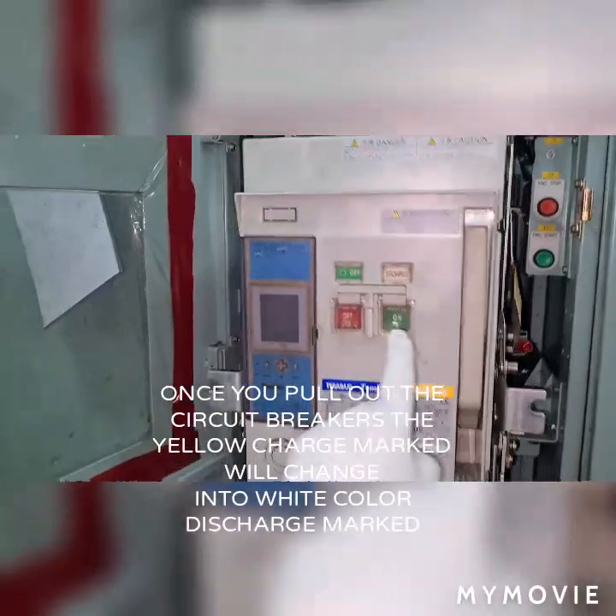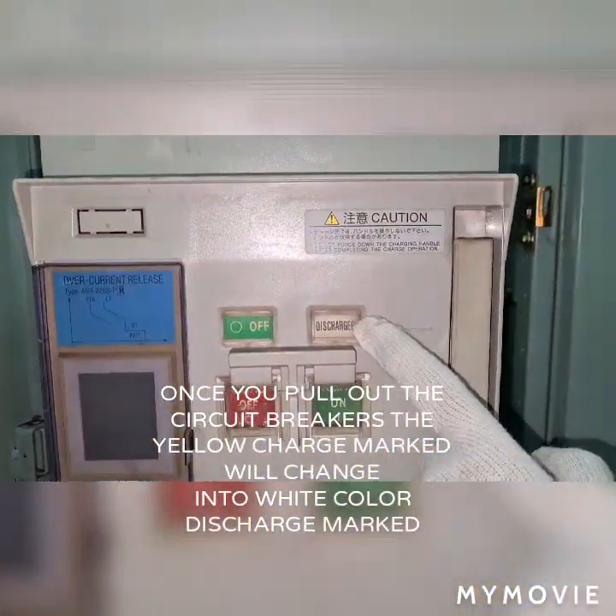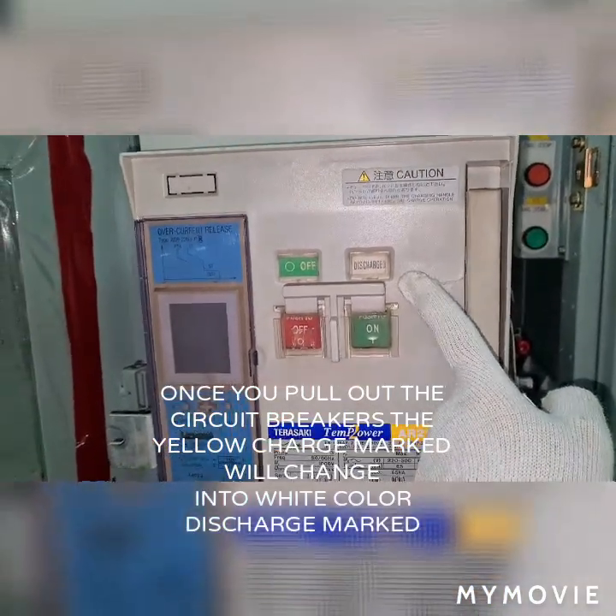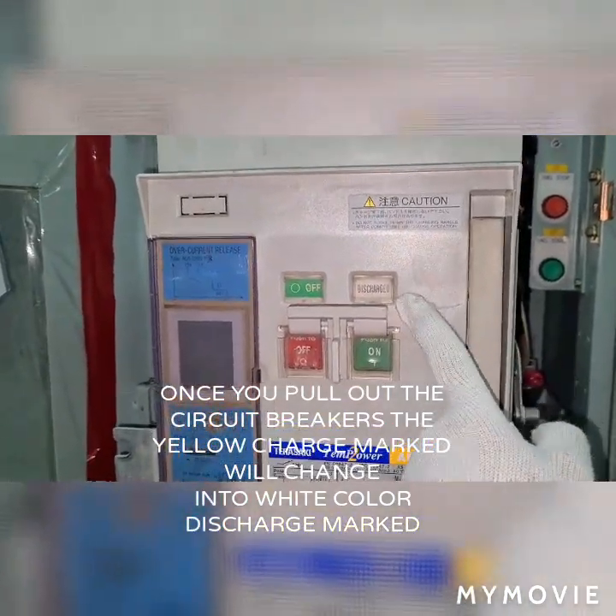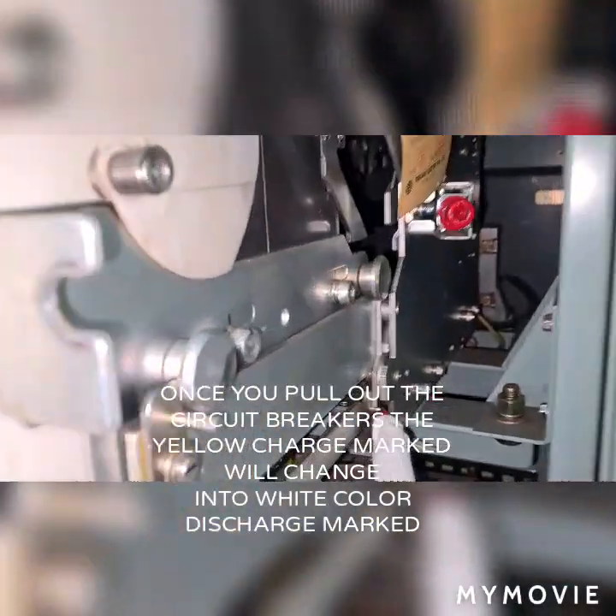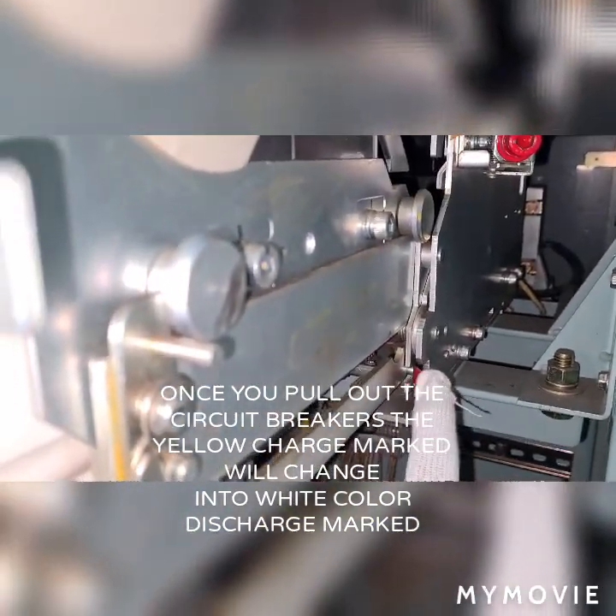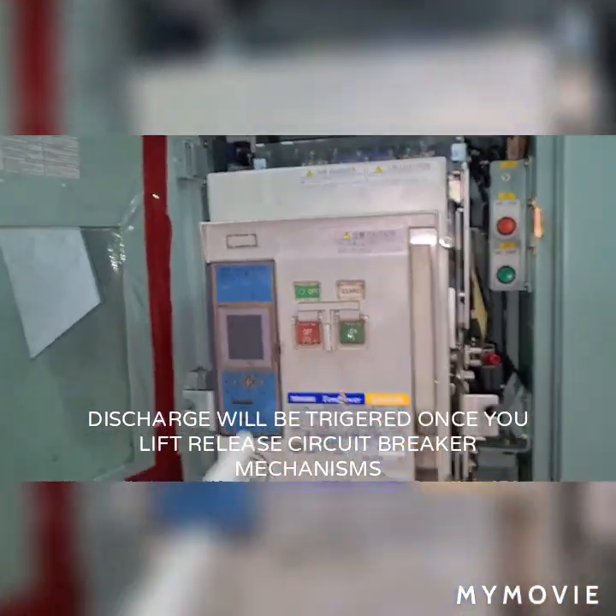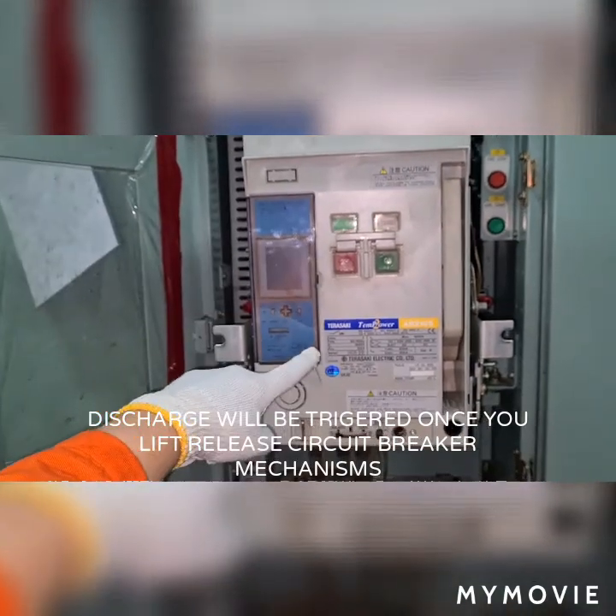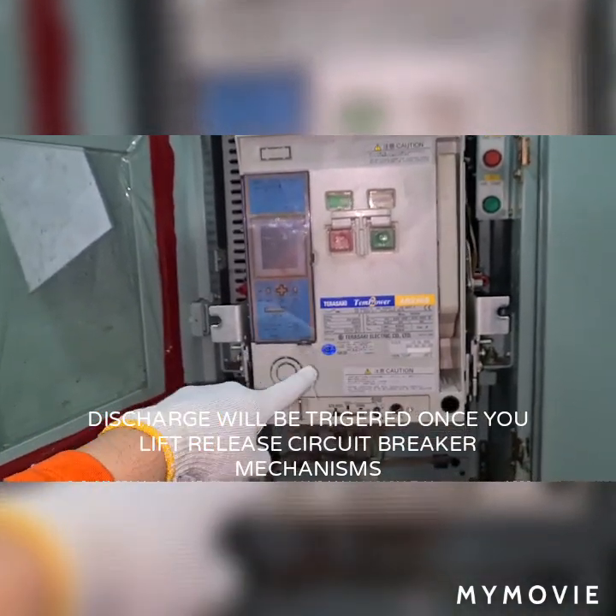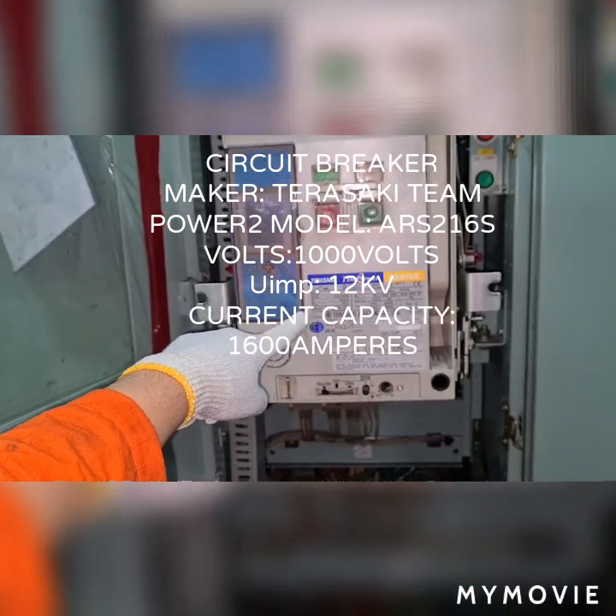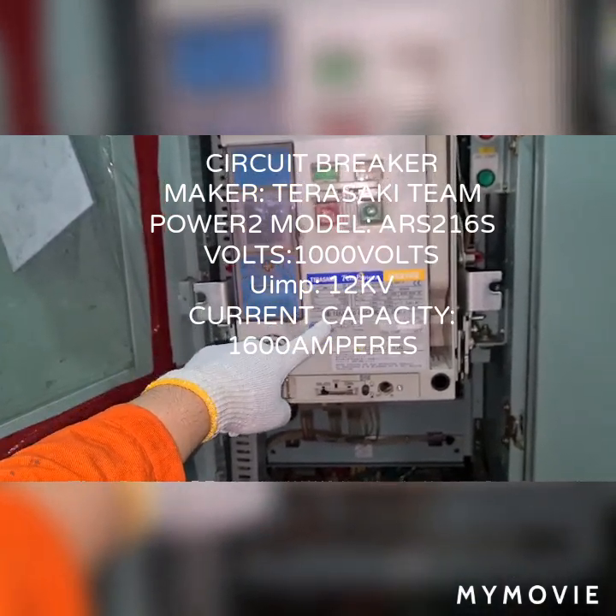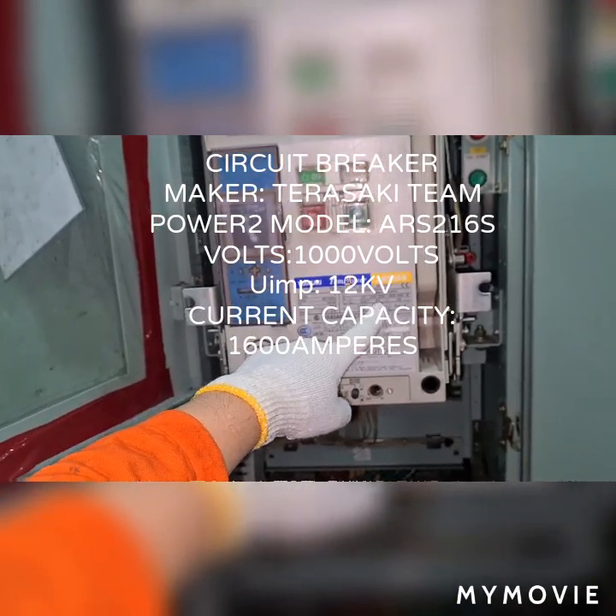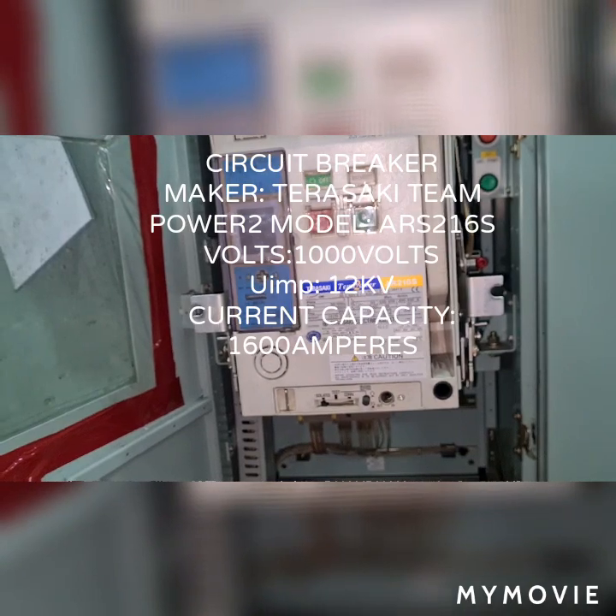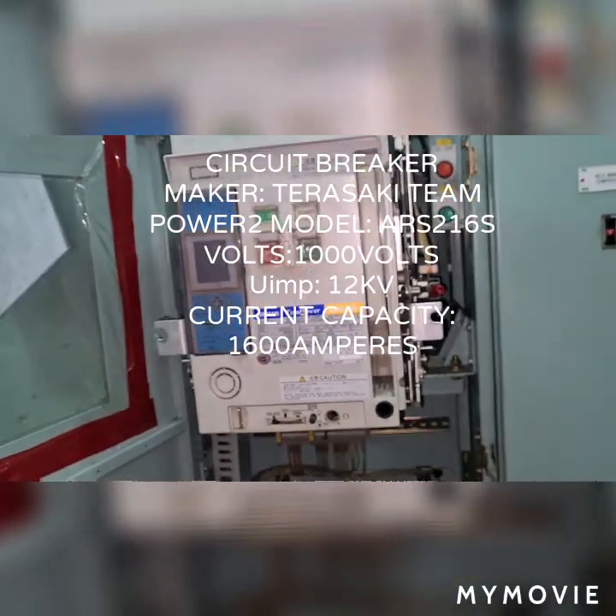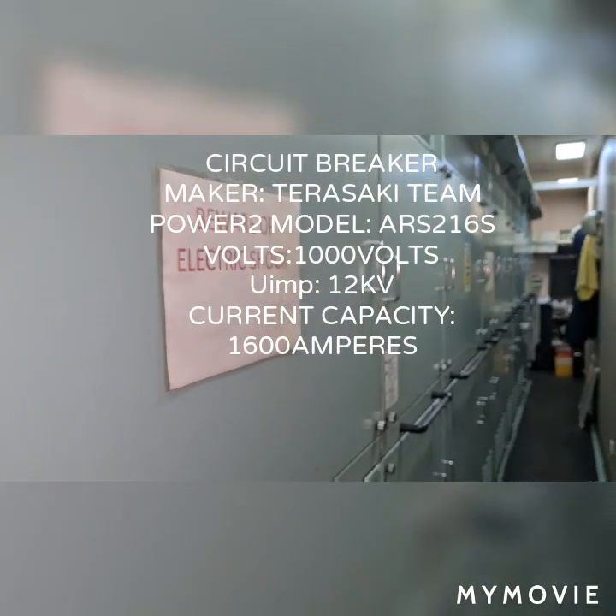Okay, I'd like to emphasize that this white colored discharge mark came up before it was a yellow colored charge mark. This comes up once we release this red color mechanism and make a little bit of a pull on the circuit breaker. On board, this is the circuit breaker I have. This circuit breaker maker is Terasaki, Tem Power 2, model ARS216S, 1000 volts with Uimp 12 kV and a current capacity of 1600 amperes.